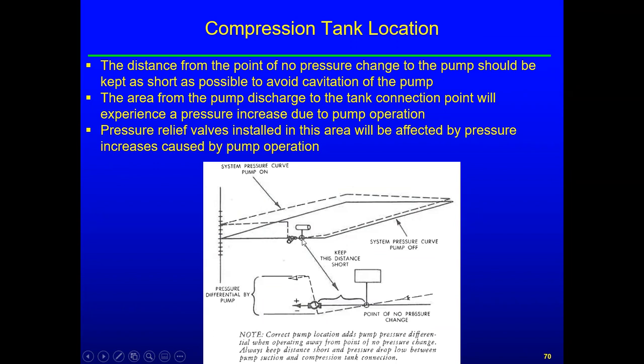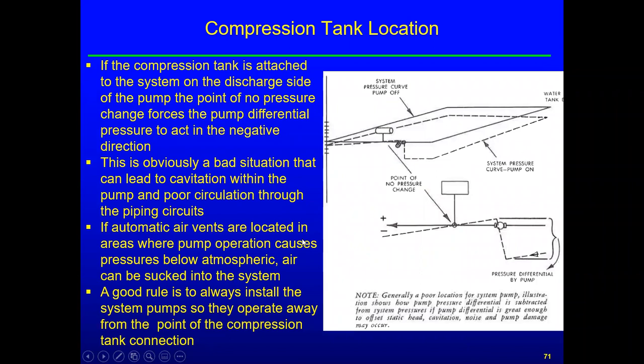Okay, so this is your first design job, and you get out there, and dadgummit, I forgot, and in my piping drawing, I connected the compression tank to the pump discharge. Well, boss, is that going to make a difference? Well, let's take a look at this and see. The answer is yes, because your point of no pressure change is here. Basically it forces that pump head to go in the negative direction. And that's a great recipe to cavitate a pump, because that pump head is going to be significant. So this is almost a guarantee that you're going to cavitate this pump, especially if this is a hot water heating system.